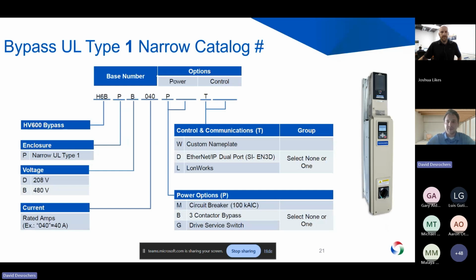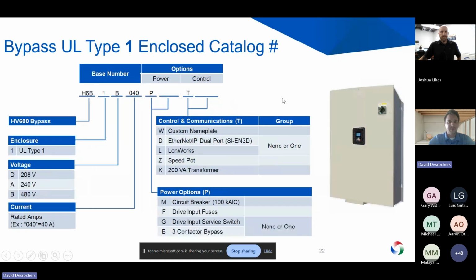This is the same kind of deal, going with the narrow configuration, trying to go narrow and tall in order to fit more on a mechanical room wall. We break the part numbers down this way. And same as the regular configured, there are a variety of power options and control options that you can include onto the drive. So basically, bypass, Type 1, then your voltage class, the rating of your amperage, and then you can build it out from there.